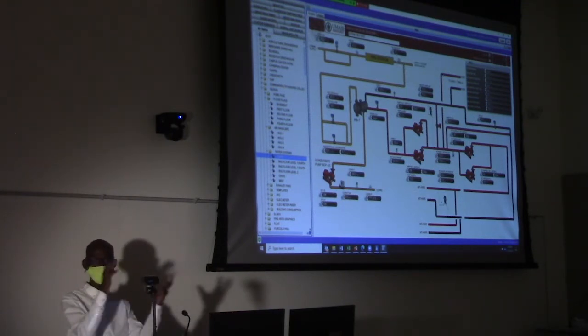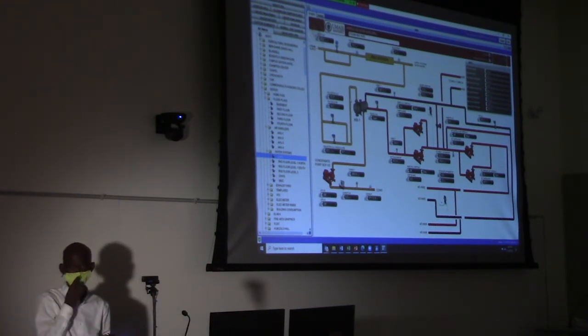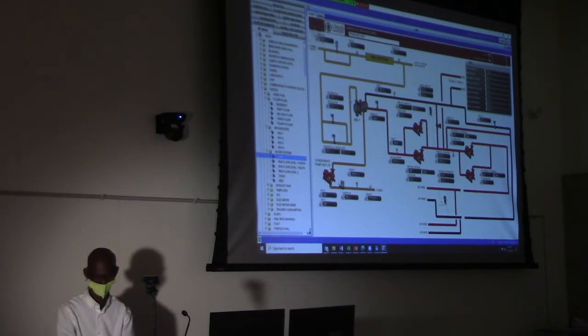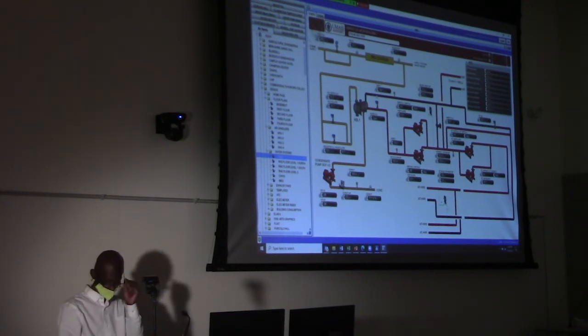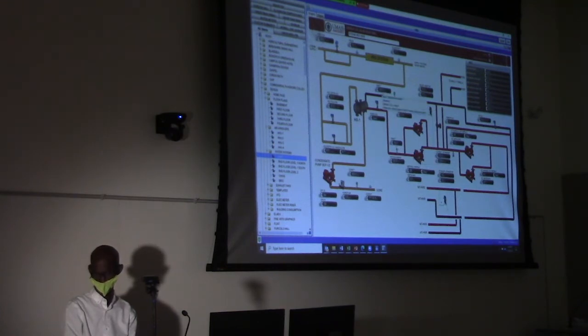Then the steam goes through a heat exchanger. It dumps all the heat into the exchanger, and the hot water coil picks up that heat from the steam and heats up the hot water. That hot water is circulated to the building. Right now, if you can see, we have hot water supply at 160 right there, and the return is 140 degrees Fahrenheit.